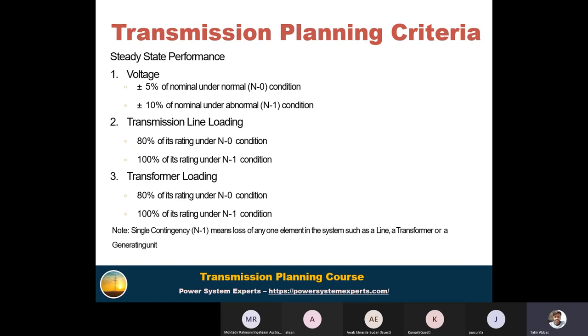Next is the transformer loading. Under normal condition its rating is under 80%, and under N minus one it is 100%. Note that I want to discuss here that single contingency means the loss of any one element. It may be a line, a transformer, or a generating unit, and it may also be a sudden loss of load. So this is a type of single contingency.